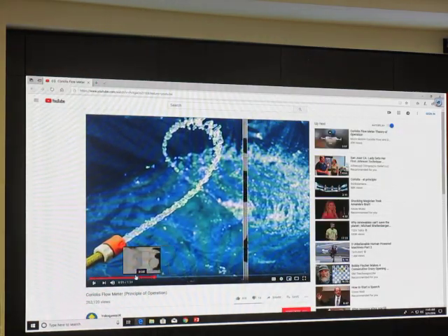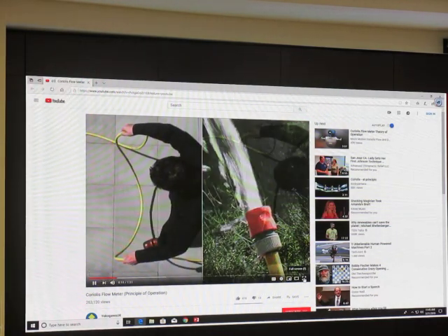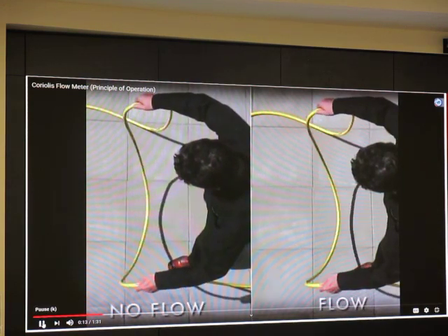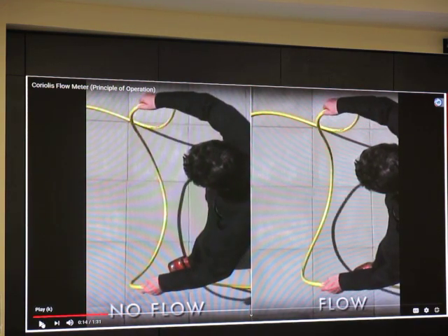Have you ever looked at what operates on this principle? Oh, okay, I want you to see this. The water is forced through the swinging hose. The hose twists as a result of the change. You see, with and without flow. Okay, this is a water hose with and without flow. When there's no flow, we swing it, it doesn't twist. See, it's kind of straight. But when there's water inside, it twists like this. Okay, so the degree that it twists depends on the flow rate. In the flow meter, angular velocity in the curved hose. That's the Coriolis effect in action.